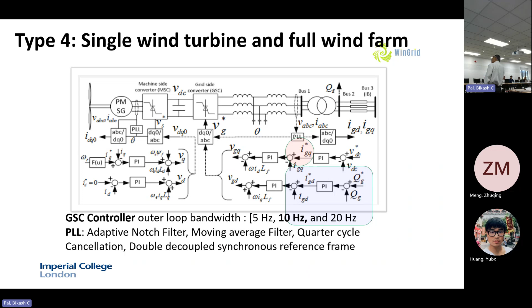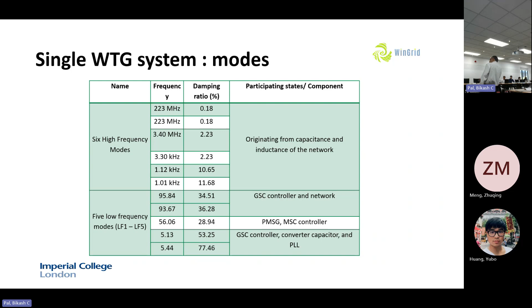Now here, about less than 100 hertz to 5 hertz, it's the grid side converter, controller, and network. And this 56 hertz is PMSG and the machine side converter, controller, gain, etc., integral part, they are contributing. And here again, grid side converter, controller, converter capacitor, as well as the DC link, as well as the PLL phase lock loop state variable. So they contribute to this frequency. This is again clear how this is happening.